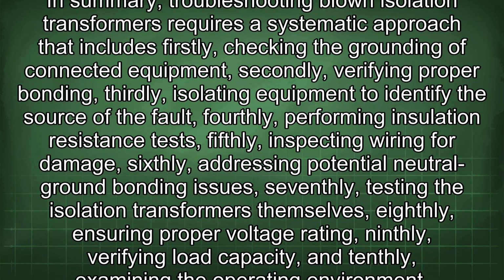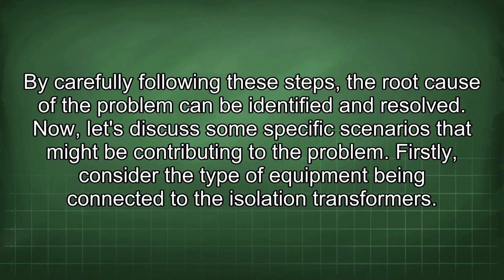In summary, troubleshooting blown isolation transformers requires a systematic approach that includes firstly, checking the grounding of connected equipment, secondly, verifying proper bonding, thirdly, isolating equipment to identify the source of the fault, fourthly, performing insulation resistance tests, fifthly, inspecting wiring for damage, sixthly, addressing potential neutral ground bonding issues, seventhly, testing the isolation transformers themselves, eighthly, ensuring proper voltage rating, ninthly, verifying load capacity, and tenthly, examining the operating environment. By carefully following these steps, the root cause of the problem can be identified and resolved.